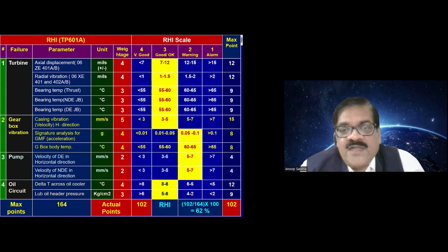What you see in the yellow background is the current position when the machine is running. Depending on that, you multiply—for example, 5 into the casing vibration reading of 3, between 3 and 5, gives 15 marks. Similarly, for axial displacement on the turbine, 4 into 3 gives 12 marks. The maximum possible score is 164, and we're getting 102 after multiplying the different parameters against where it's presently running.